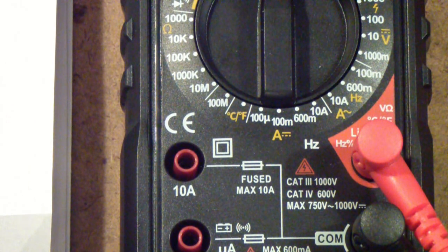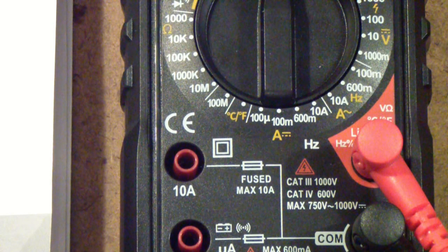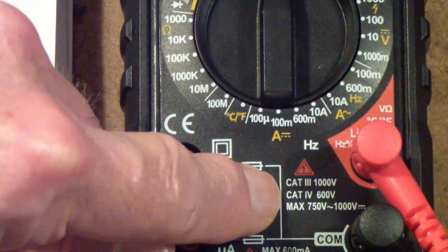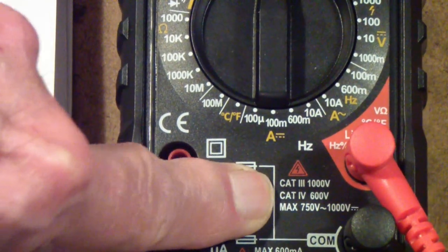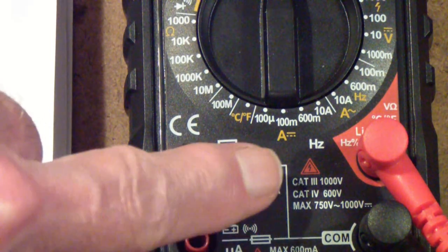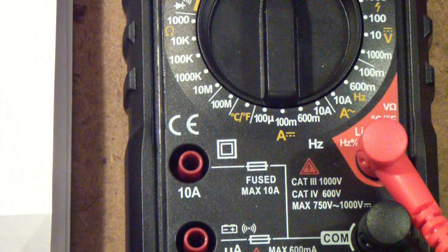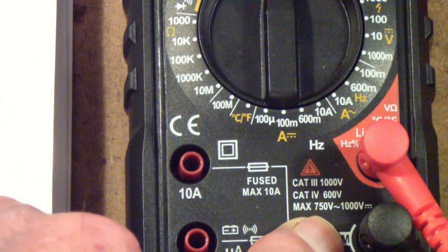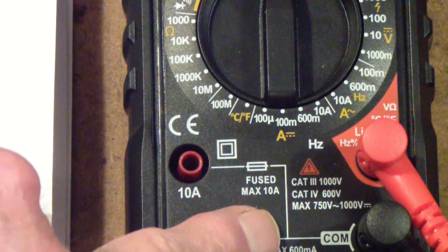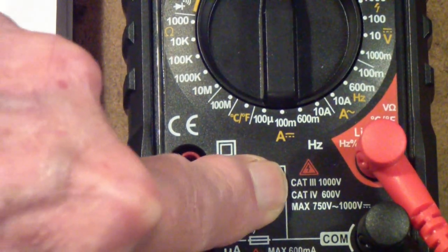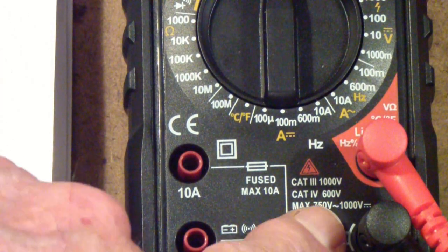Remember that even if you're working on say a 440 volt line or a 220 volt line, but you're working with inductive equipment—big motors, switches, relays, that kind of thing—the transients can be several thousand volts. So the fact that this meter is rated to 750 volts and you're only using it on a 220 line doesn't mean that you are protected unless it also has this CAT rating that will protect you against transients.